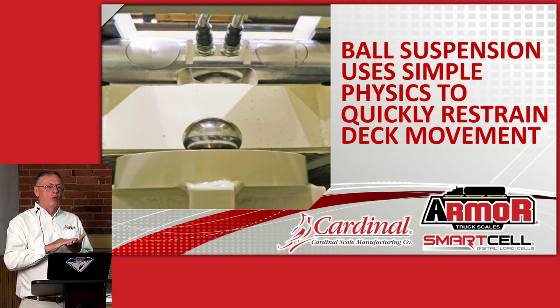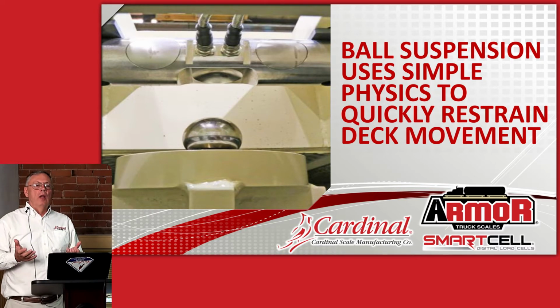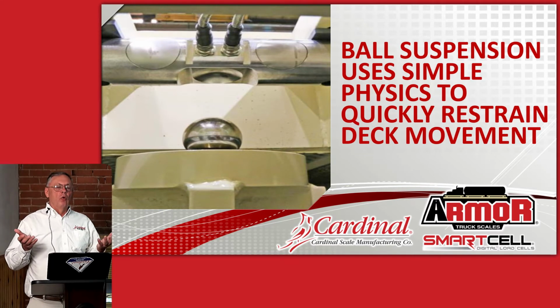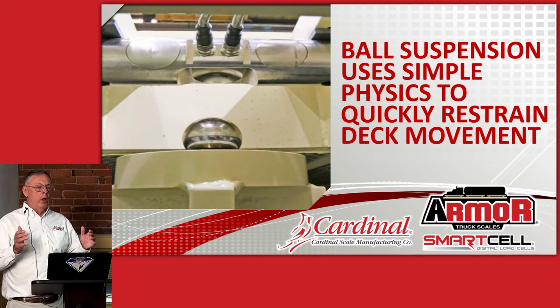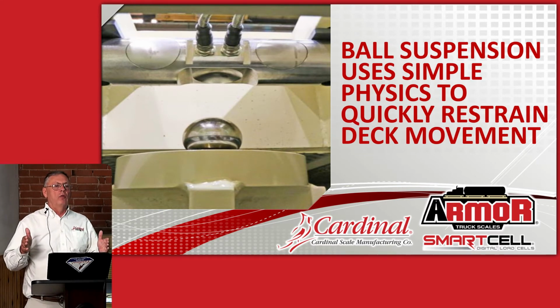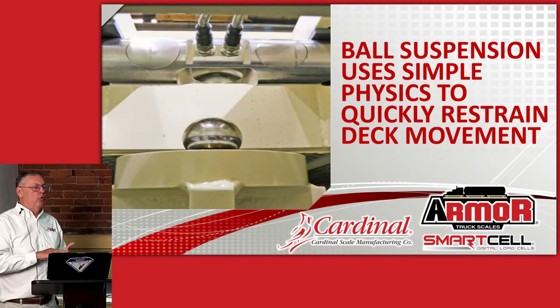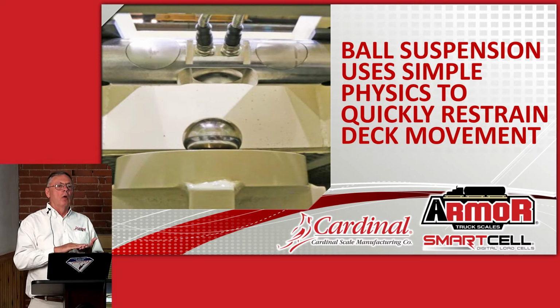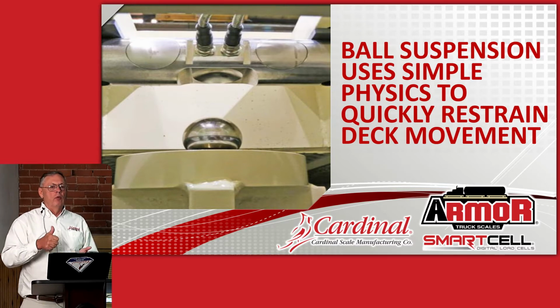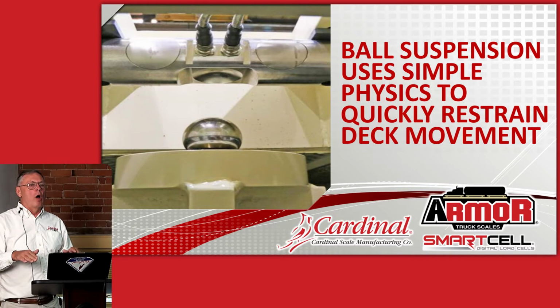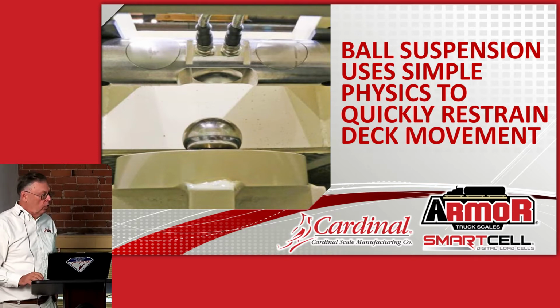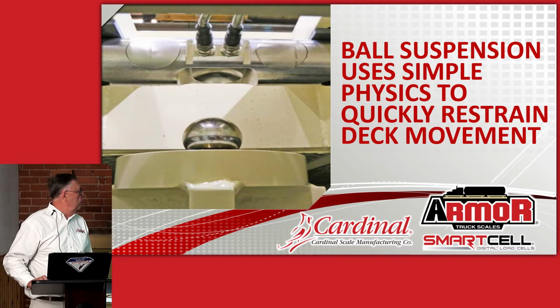And as soon as it starts rolling up the radius, it has to lift the weight of the weighbridge and the weight of the truck. So the heavier the truck is, the quicker it actually stops and comes back to rest. There's just a tremendous amount of force required to lift that weighbridge up. And as soon as that ball starts rolling up the ramp, that tremendous force pushes it back down and it rocks about twice, and you've got a stable weighbridge and get a good stable weight reading.